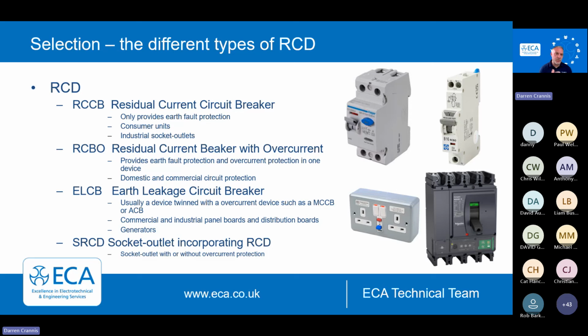So that's why special considerations need to be in place if they're in split load boards, or they might be incorporated into industrial outlets like commando sockets, for example. We have the RCBO, which I think we all love. So that's the combined one. That is protection against overload, typically BS EN 61009 series, and that's a residual current circuit breaker with overload protection, RCBO.